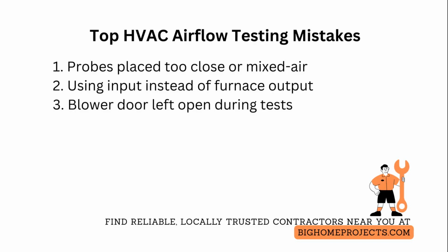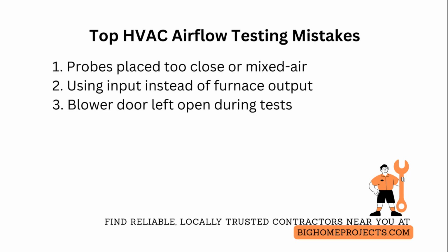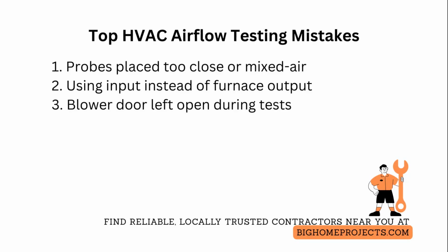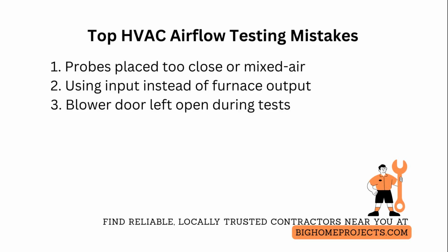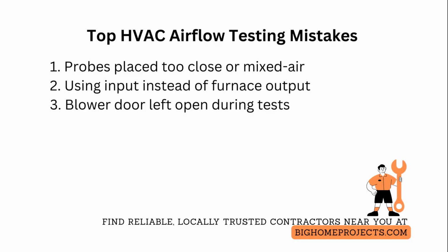One of the most common mistakes with the HVAC temperature rise formula for cubic feet per minute is ignoring furnace output and just plugging nameplate input into the equation. That ruins airflow CFM calculation accuracy on gas furnaces. Fix it by verifying steady-state efficiency with combustion measurements or manufacturer tables, and multiply input by that efficiency before dividing by 1.08 times temperature rise.